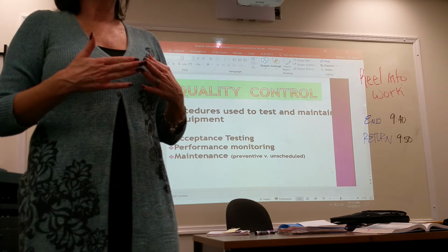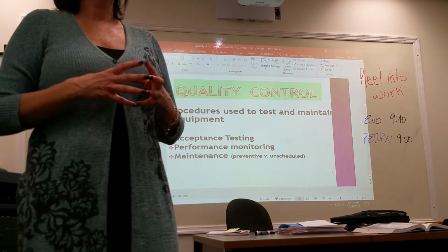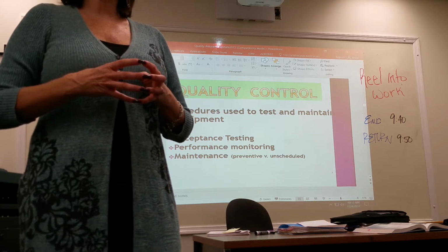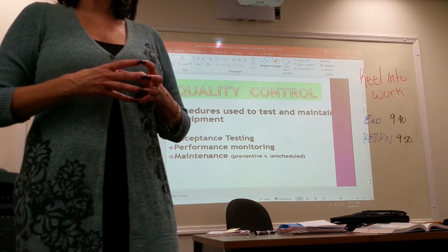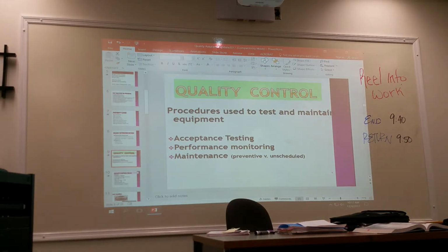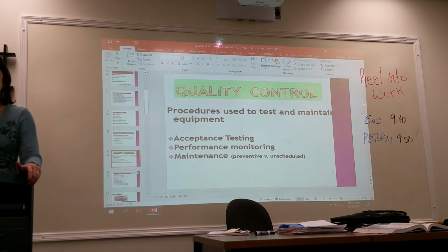Okay, so if you test something and it fails the test, what do you do then? Schedule maintenance for it. You will retest it. That's like calling the computer geek out to fix your computer and it wasn't plugged in. Always retest to make sure that you didn't do something wrong. And in fact, that's what you're supposed to do. Retest it again and make sure that it is out of compliance, that you didn't do something wrong with the testing, just to confirm it.